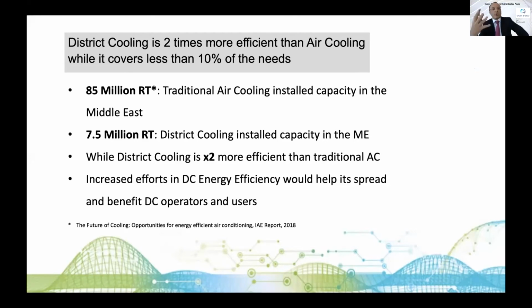Since the beginning of this webinar, we heard about how district cooling is going through challenging times, as compared to the traditional AC, I would say. So here, just some numbers. In the Middle East, we have about 85 million refrigeration tons of installed air cooling capacity by traditional means, and about 7.5 million RTs of district cooling. So it represents a little bit less than 10%, and probably in cities like Dubai, we can reach barely 20%. So this is a kind of AC-DC paradox where, while the district cooling is more efficient, probably 2 times more efficient than the traditional air conditioning, its penetration and its contribution to the overall cooling in the Middle East is still quite low.